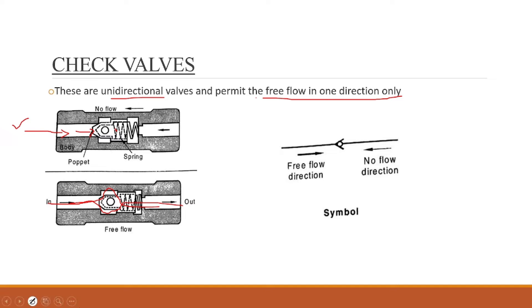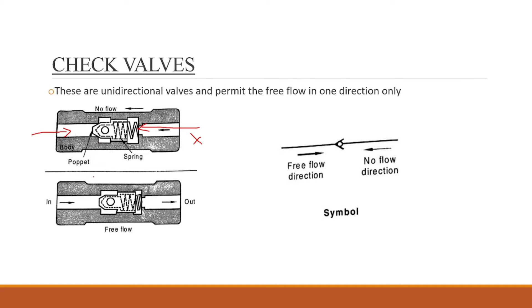Flow can pass through the check valve in the free-flow direction. However, if you want flow in the opposite direction, the spring force plus the fluid pressure on the poppet presses the poppet seat closed. So no flow is possible in the opposite direction. Flow is only permitted in one direction — that is the check valve.